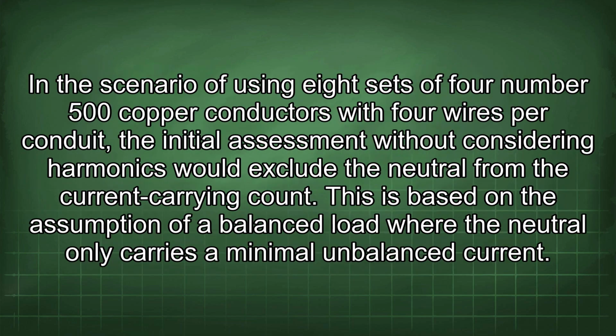In the scenario of using 8 sets of 4 number 500 copper conductors with 4 wires per conduit, the initial assessment without considering harmonics would exclude the neutral from the current carrying count. This is based on the assumption of a balanced load where the neutral only carries a minimal unbalanced current.